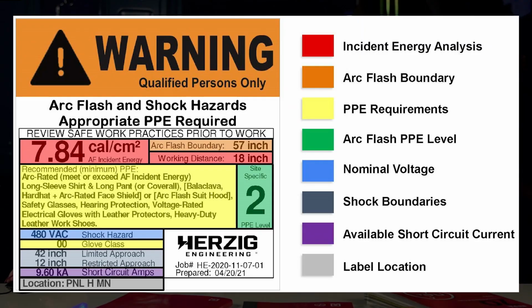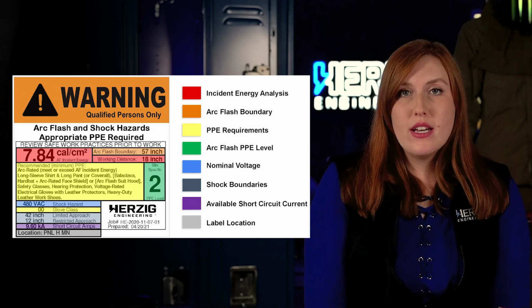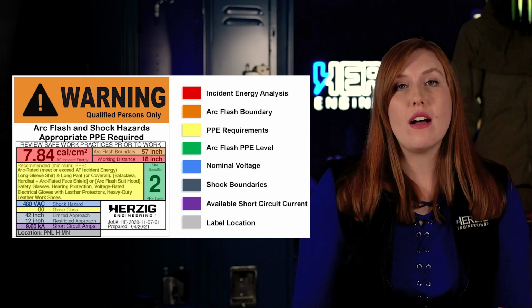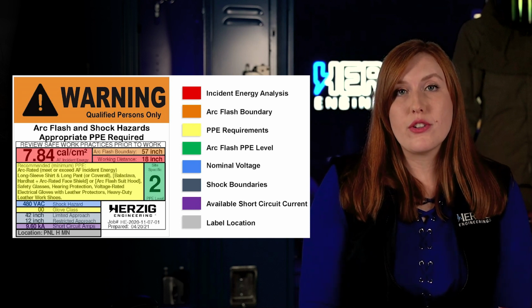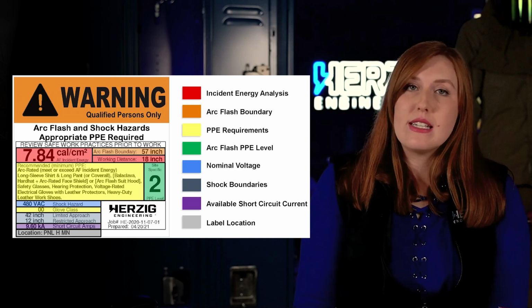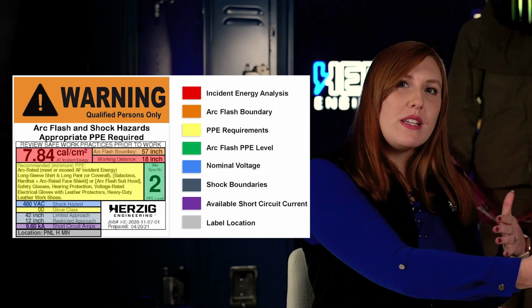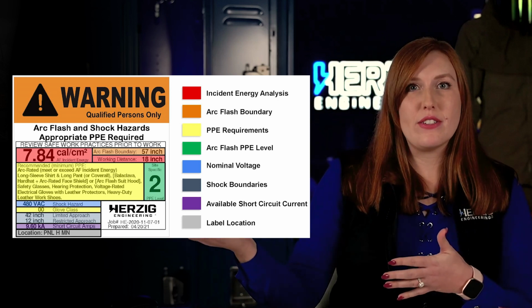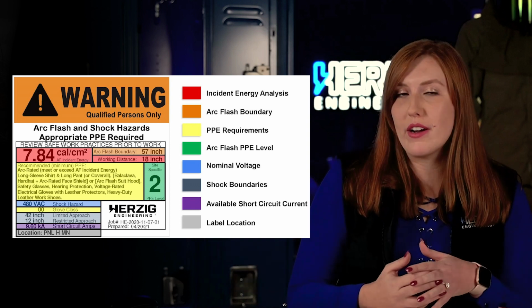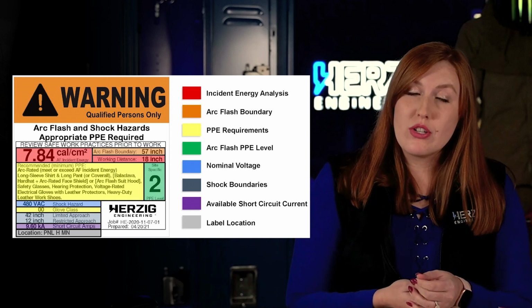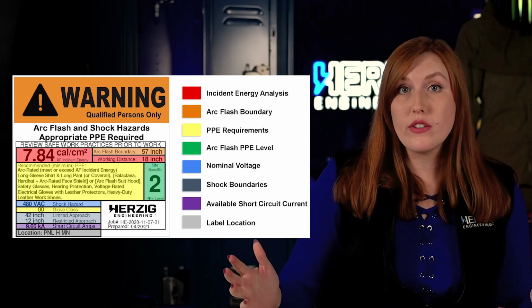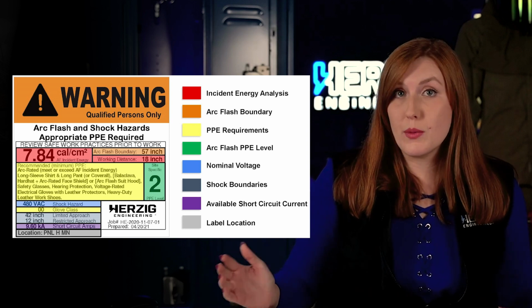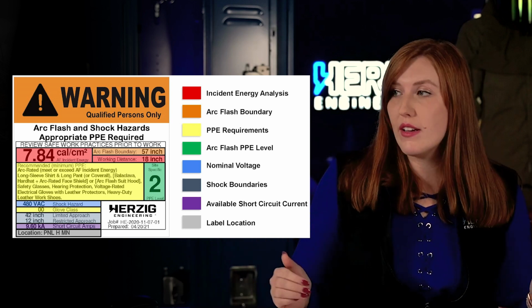So that is just an example of what our warning labels would look like once they are printed for you. And it's explaining what the information entails. So the result of the analysis is called the incident energy: calories per centimeter squared, meaning how hot or how severe over a surface area that arc flash burn potential will be. And the working distance, so it's at an 18-inch working distance. If you're standing in front of a piece of equipment about 18 inches away, this is how much of a hazard you're facing, because it's based on heat dissipation from that arc event. And then we've got the arc flash boundary, which is how far out that arc flash can still hurt somebody. So think of that as kind of the blast radius. You want to keep people out of the arc flash boundary in any direction, not just directly in front of the equipment.